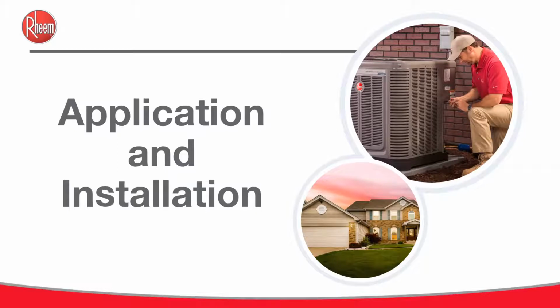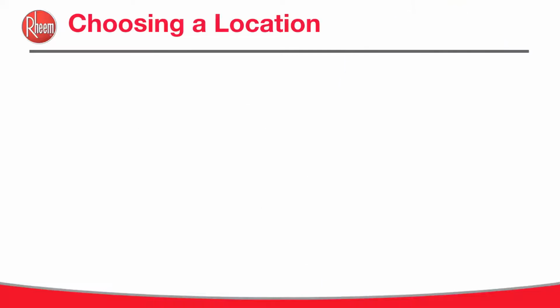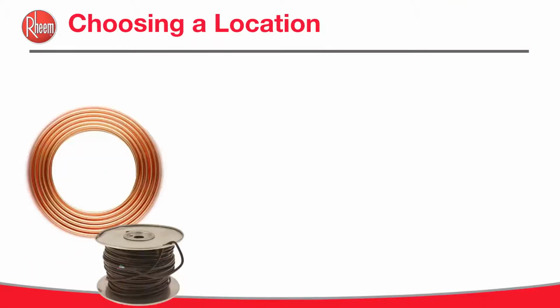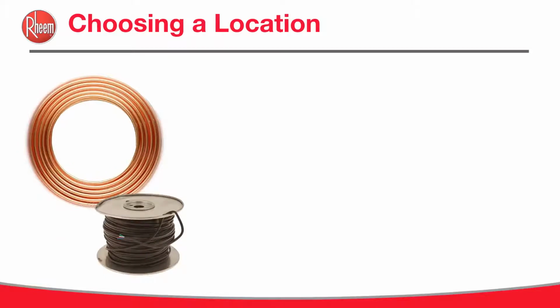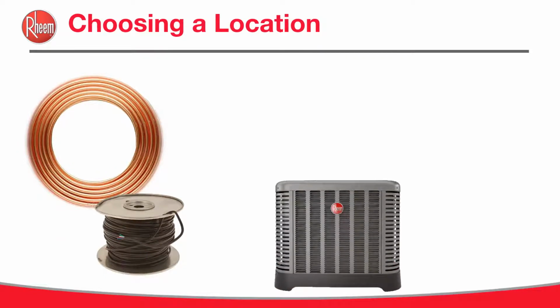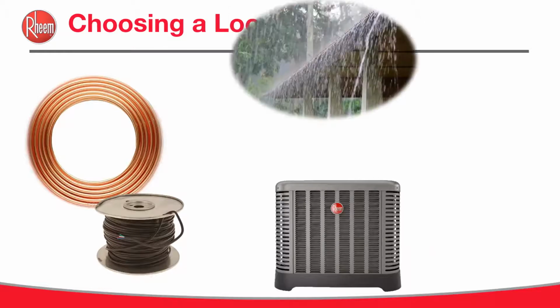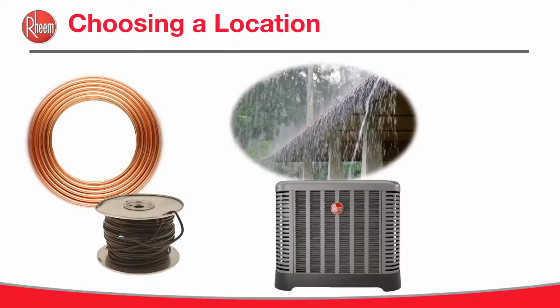Okay, let's look at applications and installation. This includes everything from choosing a location, proper tools and refrigerant, replacement units, indoor coil, interconnecting tubing. So choosing a location is important to keep refrigerant tubing and wire as short as possible. Locate the unit so water runoff will not create issues. Locate the unit away from the drip edge of the roof.